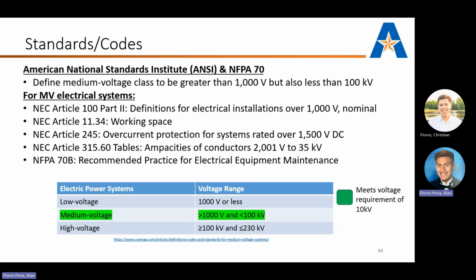This includes more articles we wanted to cover, such as NEC Article 100, Part 2, which gives definitions for electrical installations over 1000 volts nominal. We also have Article 110.34, covering the working space for separating low and high voltage devices. Article 245 covers overcurrent protection for systems rated over 1500 volts DC, and Article 310.60 tables include ampacities for conductors from 2001 volts to 35 kilovolts. Lastly, NFPA 70B, which we mentioned, also has a section recommending practice for electrical equipment maintenance.